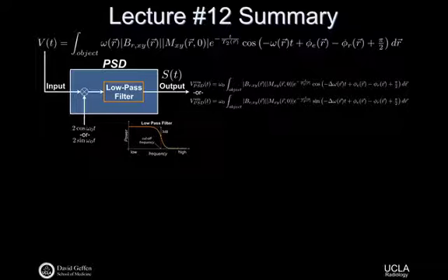And so I think at the end of the last lecture, we had worked our way through this cosine-detected, phase-sensitive detected signal, if you will. And so again, by the time we work through these steps, it actually ends up being really a delta omega R. And I misspoke a little bit. The delta omega R is what tells you about the frequency difference at a particular location. The frequency difference at isocenter would be what? Zero, right? So then we're just talking about having frequency depend on spatial position.